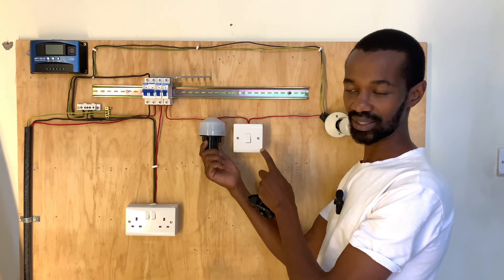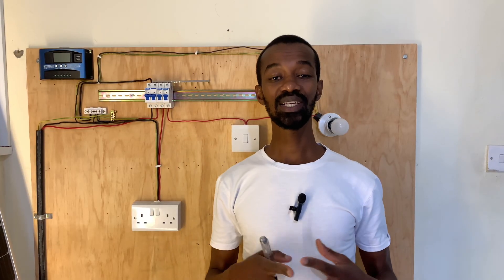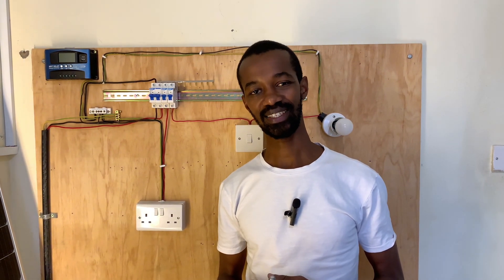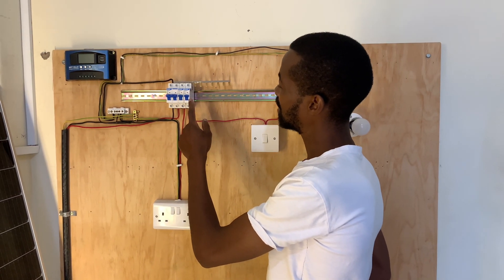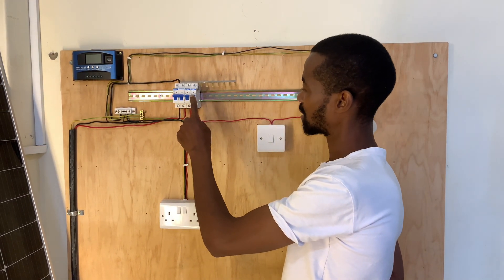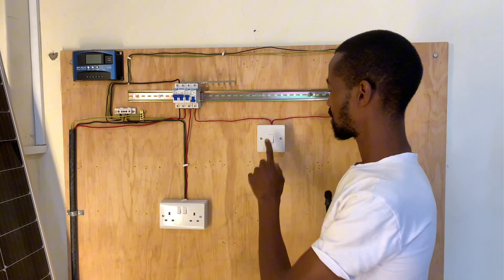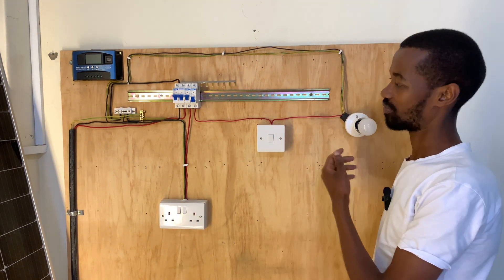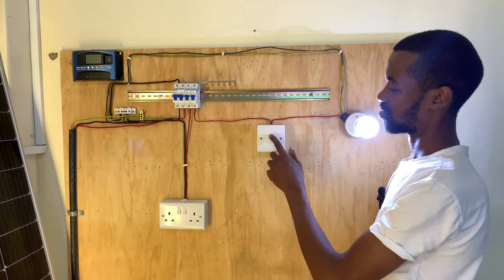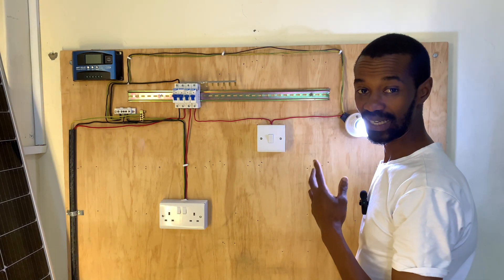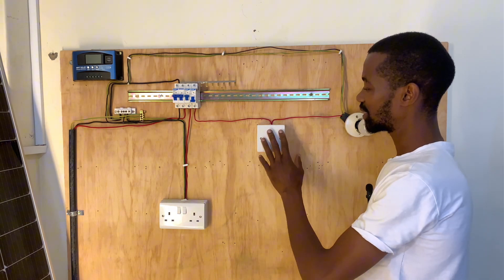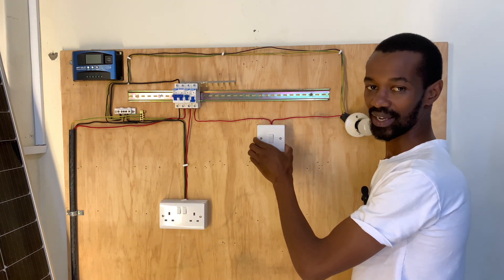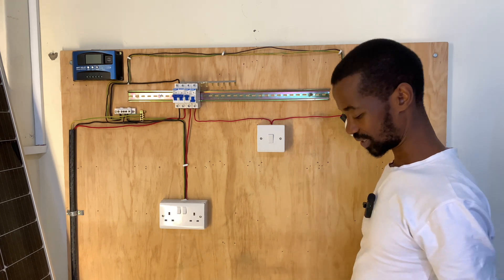To be on the safe side, I will first start by switching off the entire light circuit. My circuit is activated by this MCB, which is a six-ampere breaker. When I turn it off, my light will be off; when I turn it on, my light is on. So to make sure that I turn it off, I do so at this particular point here. Now I will get rid of this entire switch.